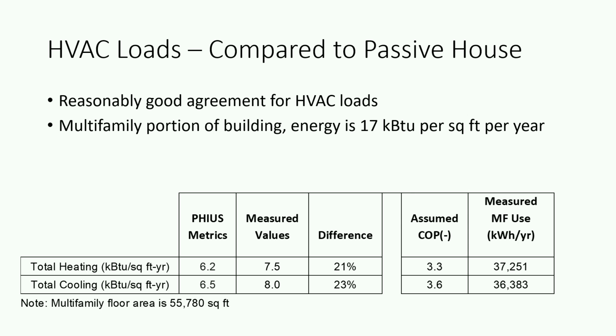The other thing I'll note is, just like we talked about, when your building gets very good, it turns out heating and cooling are about the same, right? So the energy use, and this breakout I could not do perfectly because I measured heat pump energy use, and as you'll see in some of the graphs, there's a lot of mixed heating and cooling in the building. But to the best of my ability, I estimate about half went to heating and half went to cooling.